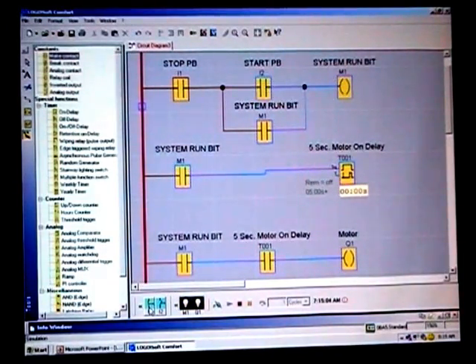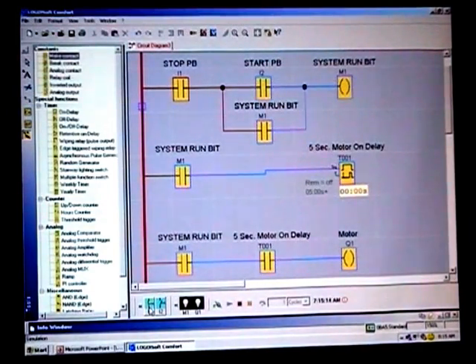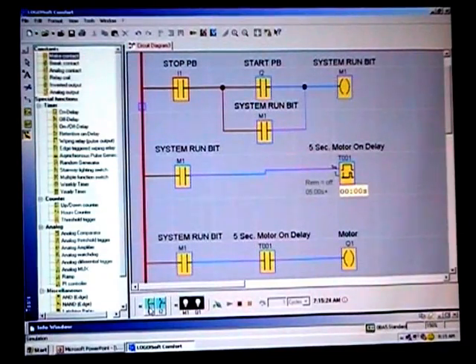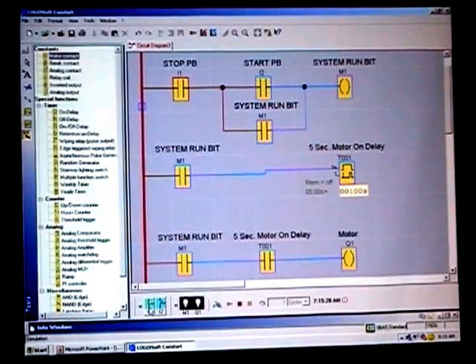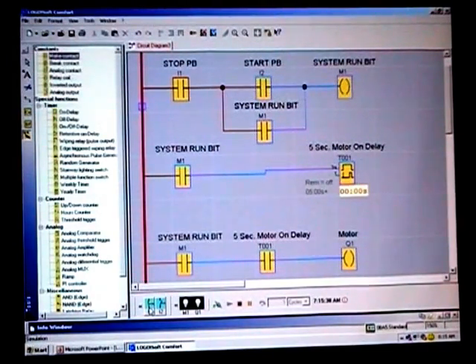Why is that awesome? In a hardwired solution you'd need a timer relay, maybe another contactor. But if start, stop, and motor are already wired to a PLC, did I add any extra hardwired components to use the timer in the program? No — it's the exact same physical circuit as if the timer wasn't there.